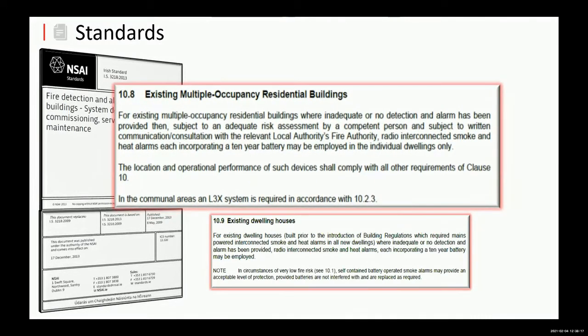So if we look at 10.8 of the Irish standard, it looks at existing multiple occupancy residential buildings. We're looking at apartment blocks here, basically. For existing ones, where this came out of really was, I suppose, when we had the boom, we were building an awful lot of apartment blocks, and then suddenly the bust came and apartment blocks weren't finished. NAMA took them over, and then NAMA started to bring them to the marketplace again, but the standard of fire detection within those apartments wasn't up to the standards of the day or the present day standards. And you're now looking at a way of extending the system within the apartments themselves. Most of these were finished off, ready for sale. So the thought of surface wiring or mini trunking or whatever going across ceilings was a no-no. So they looked at the 10-year battery operated units with the RF interconnection. And this is what they came up with.